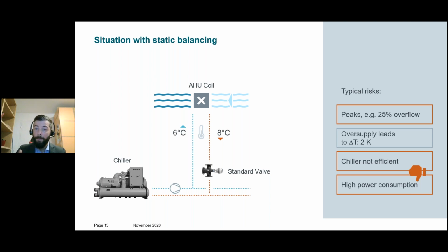And in this case, the return temperature is lower because there's no proper exchange of heat. And the delta T then gets lower. For instance, if the delta T gets reduced by 2 degrees, the chiller loses efficiency by a significant amount. And the exact amount of lost efficiency depends on the chiller and on the specific duty point of the system.